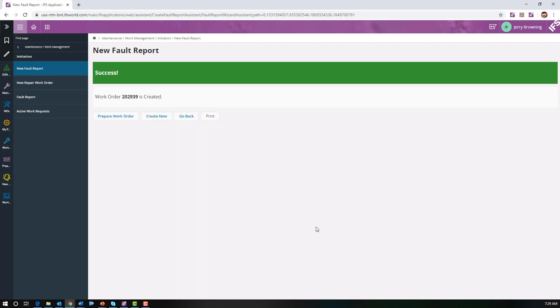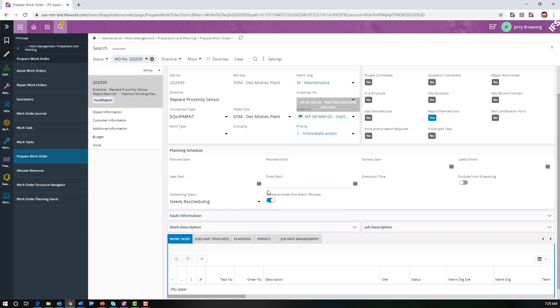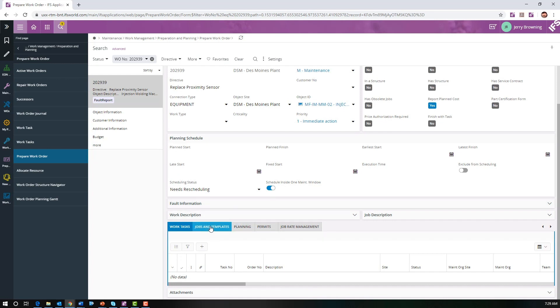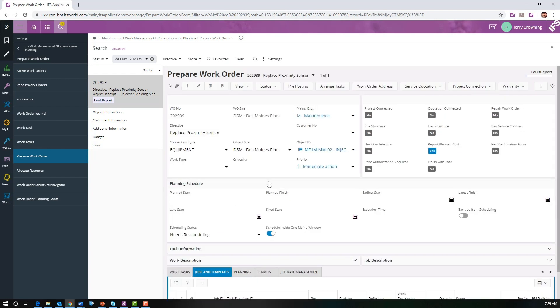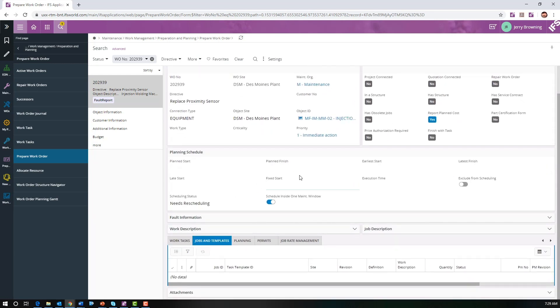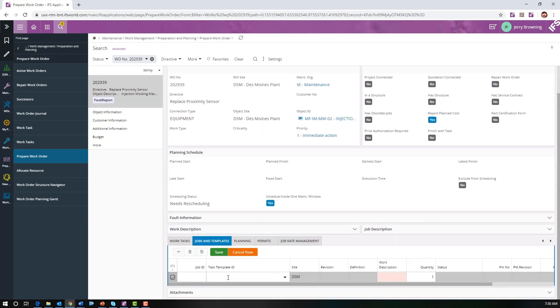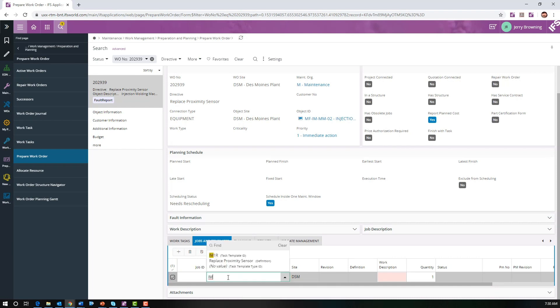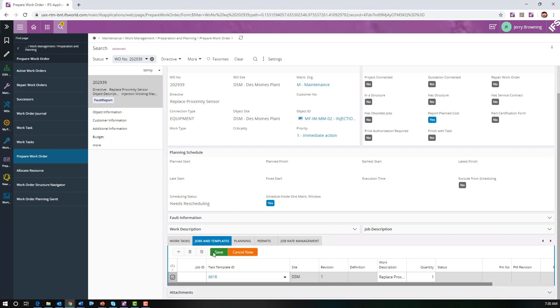Now we've created the fault report and it's generated work order number 202939. Let's look at the work order. On the work order we're going to go down to Jobs and Templates, do a new, enter the task template ID, and save.